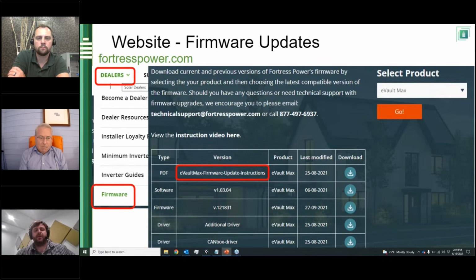The eFlex and eVault Max ship with firmware to communicate with Victron, but you never know when we'll have an updated feature, or if there's an inverter manufacturer we're converting from Modbus over to CAN bus, so for that functionality you need the firmware update tool. It's also useful for system commissioning, to confirm all the batteries are on and functional, which can speed up your commissioning process even if you're not updating firmware.